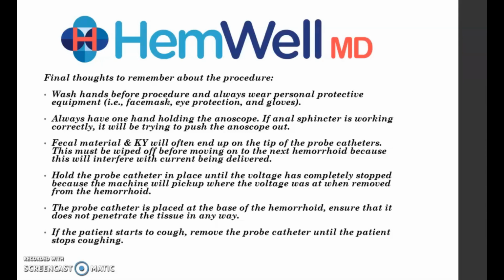Number 3, fecal material or KY lubricant will often end up at the tip of the probe catheters. This must be wiped off before moving on to the next hemorrhoid because these will interfere with the current being delivered. Number 4, hold the probe catheter in place until the voltage has completely stopped, because the machine will pick up where the voltage was when it was removed from the hemorrhoid. Number 5, when treating, the probe catheter is placed at the base of the hemorrhoid. Take care that it does not penetrate the tissue in any way. And finally, if the patient starts to cough, remove the probe catheter until the patient stops coughing.